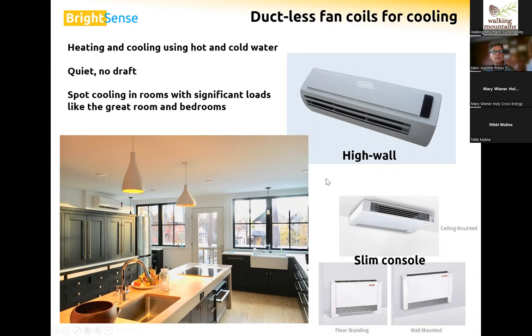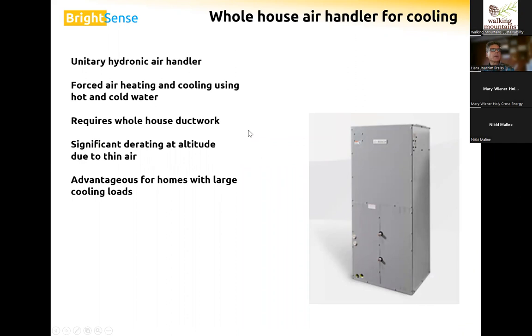Another option for cooling is whole house air handlers, unitary hydronic air handlers. So this is basically similar to this fan coil. It has a heat exchanger and a fan built in, only that this unit requires a whole house ducted system that brings the cool air to the respective rooms. So this is a lot more involved, because this is a larger blower, 2-ton, 3-4-ton capacity.